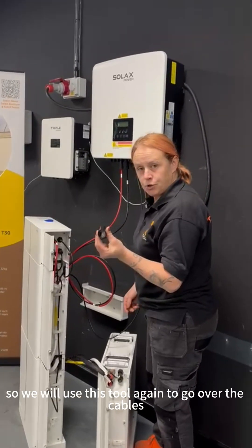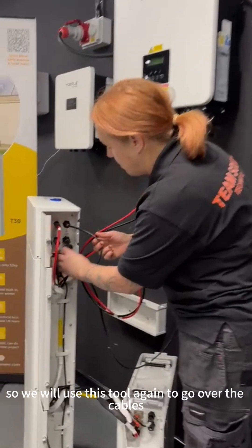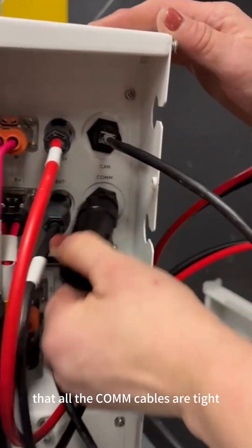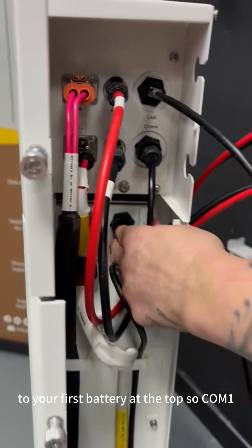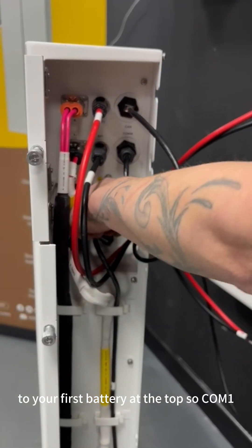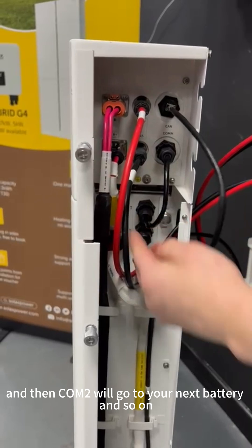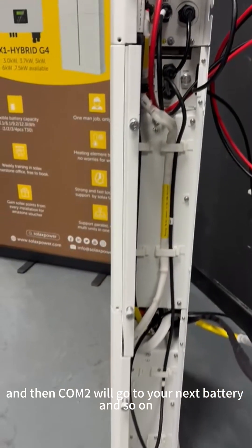Then we can screw the bottom cap back up to make this IP rated. We'll put this end back through the grommet and into the CAN port. As you can see, we heard a click and that is now in nice and tight. We'll use this tool again to go over the cables just to verify that all the comms cables are tight. We've got comms cable from the BMU to your first battery at the top, comm one, and then comm two will go to your next battery and so on.